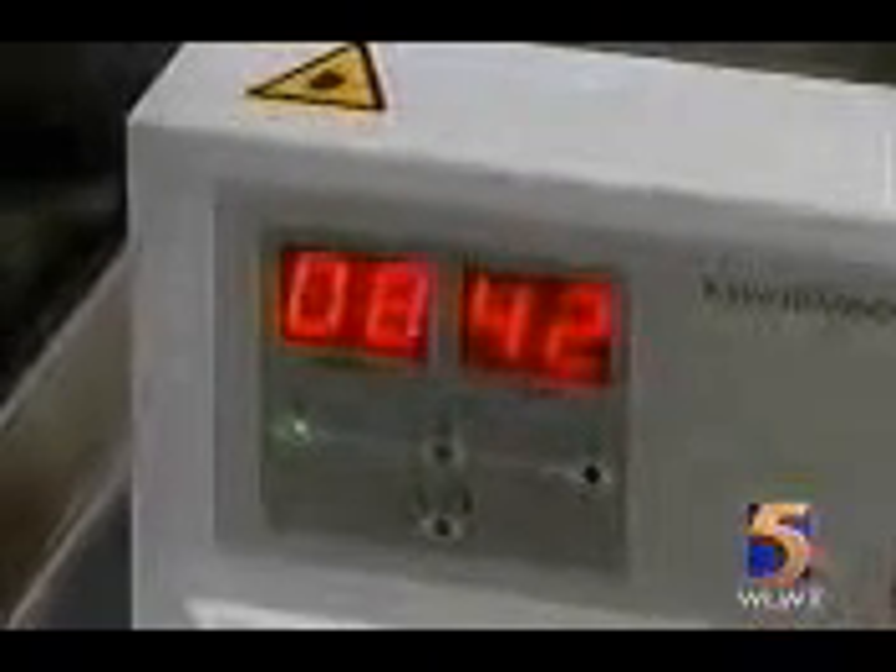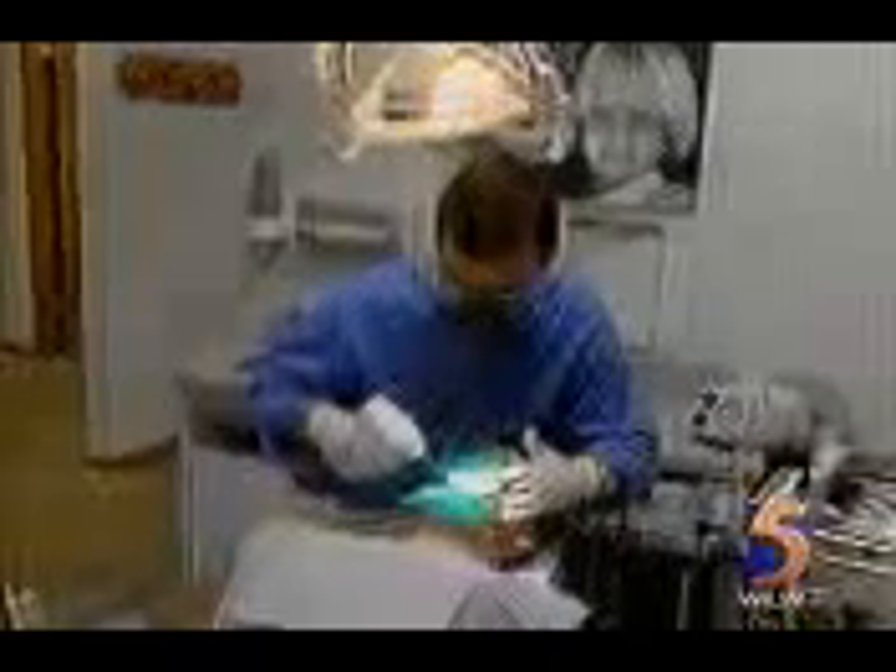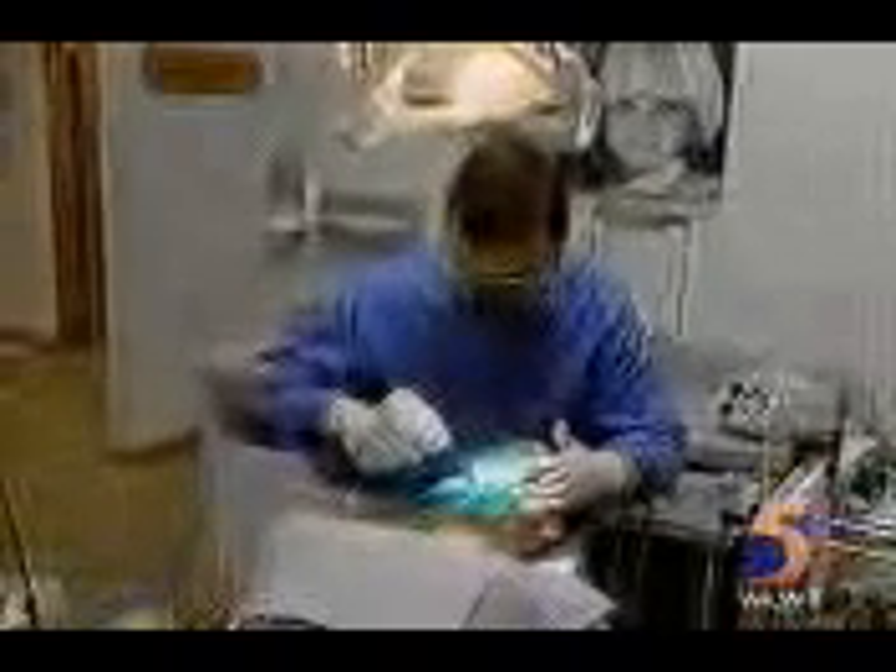That's the KaVo Diagnodent in action, catching tooth decay before it becomes a cavity. The laser light penetrates about two millimeters into the tooth, and fluorescents are reflected back. A measurement over 30 means decay.